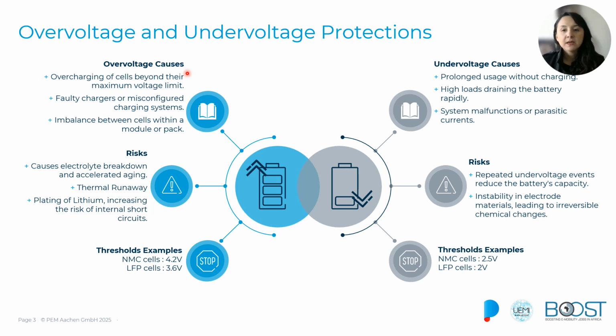To prevent this, the BMS is constantly monitoring the voltage of all of the cells, and if any of these cells approaches or exceeds this upper voltage limit, the BMS will disconnect the charger, and this ensures that the voltage will not continue rising. Some of the consequences of overvoltage might include, for instance, the electrolyte breakdown, which accelerates the cell degradation. Also, some other consequences are lithium plating, for instance, that increases the risk of internal short circuits, as well as the potential of thermal runaway that could lead to catastrophic failures and explosions in our system.